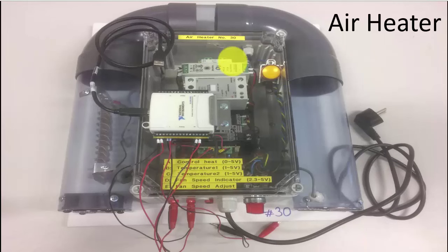Here is something you need to know about the PID controller. This PXG5 Fuji PID controller uses a so-called proportional band. So you need to use this formula to convert the value from proportional band to the ordinary KP that we use inside LabVIEW in order to compare the results. Let's assume we are using the built-in PID controller in LabVIEW, and we set KP equal to 0.8. Then in order to test the same value inside the PID controller, we need to set the proportional band equal to 125, like this.